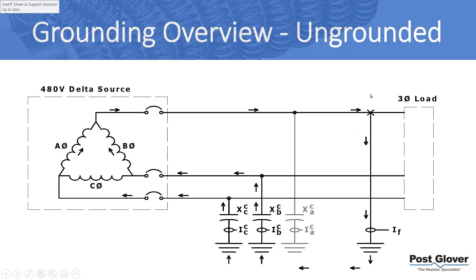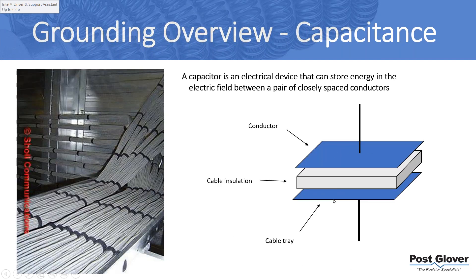Let's start with ungrounded systems. We have a ground fault on phase A in a three-phase three-wire system. It's not intentionally grounded, so how does it complete the circuit? The only path it has is through what we call the system's capacitance. A capacitor is two conductors with an insulator in between — parallel cables, motor windings, almost everything in your system has a very small level of capacitance that adds up. That's a naturally occurring ground fault path — the capacitive charging current.